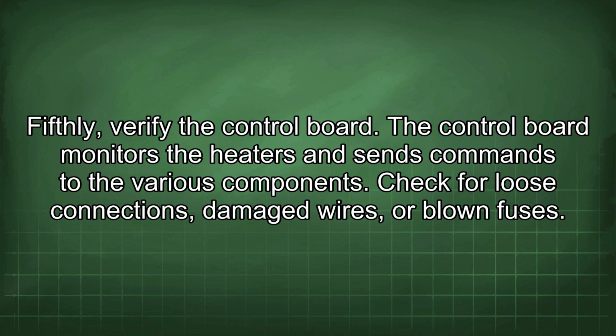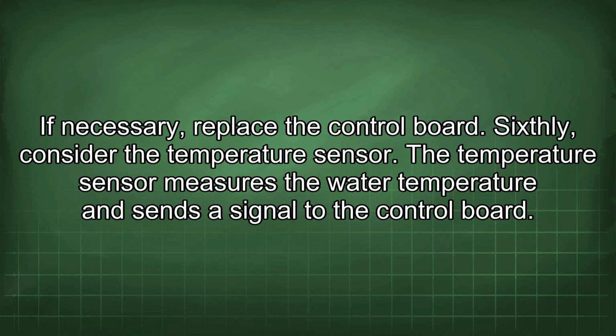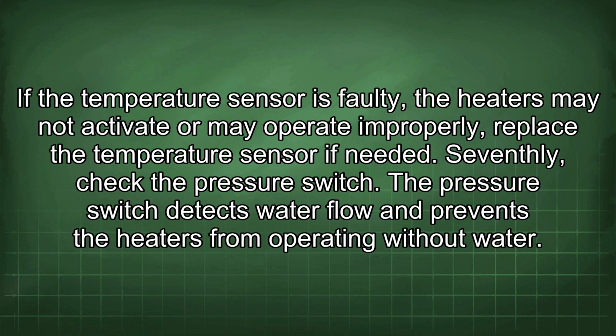Fifthly, verify the control board. The control board monitors the heaters and sends commands to the various components. Check for loose connections, damaged wires, or blown fuses. If necessary, replace the control board. Sixthly, consider the temperature sensor. The temperature sensor measures the water temperature and sends a signal to the control board. If the temperature sensor is faulty, the heaters may not activate or may not operate properly. Replace the temperature sensor if needed.